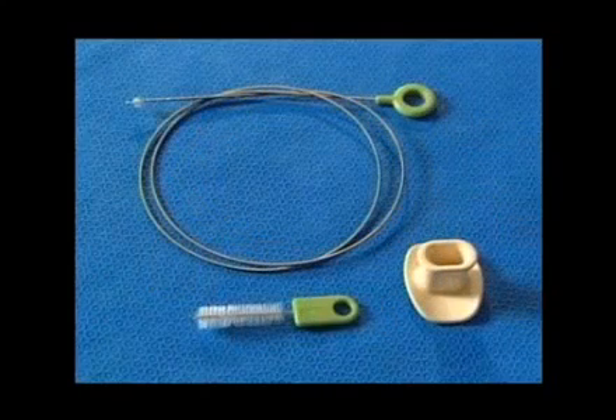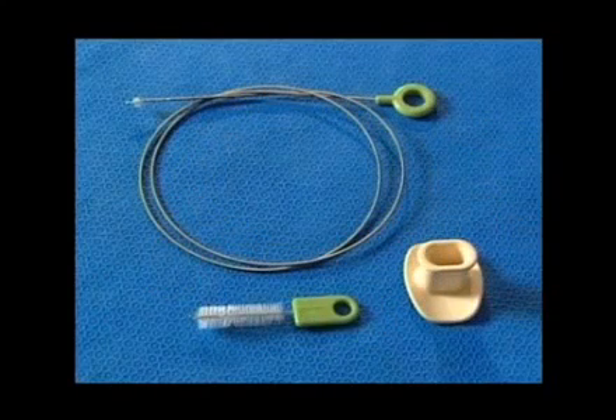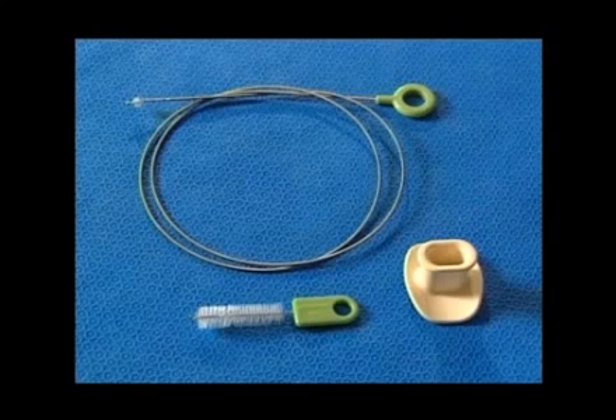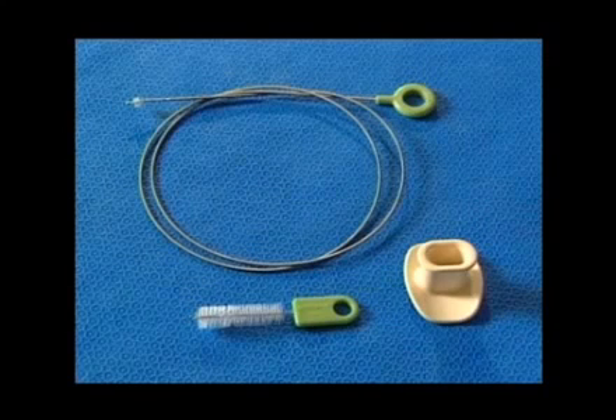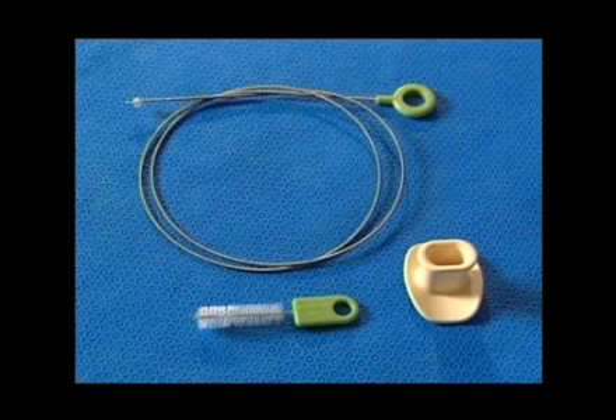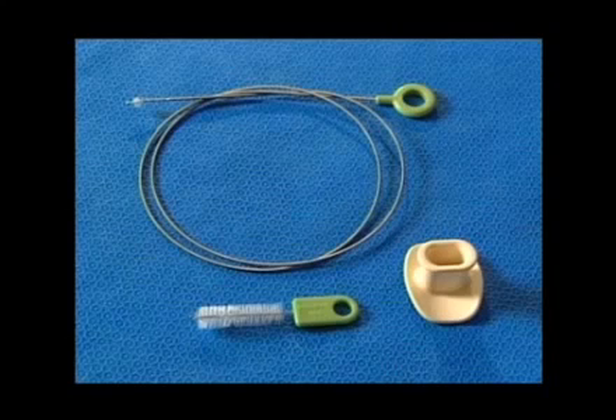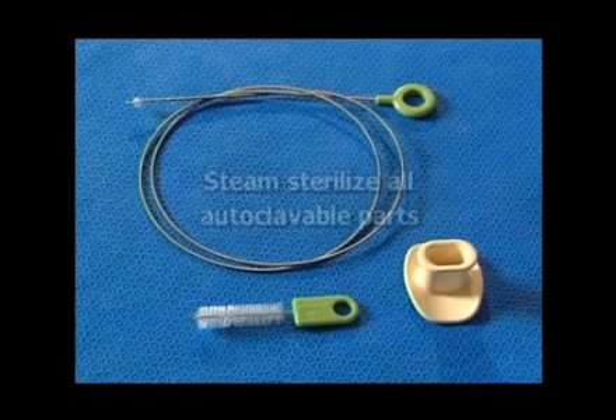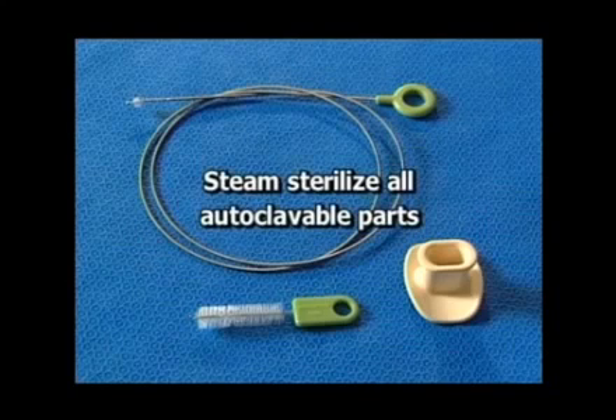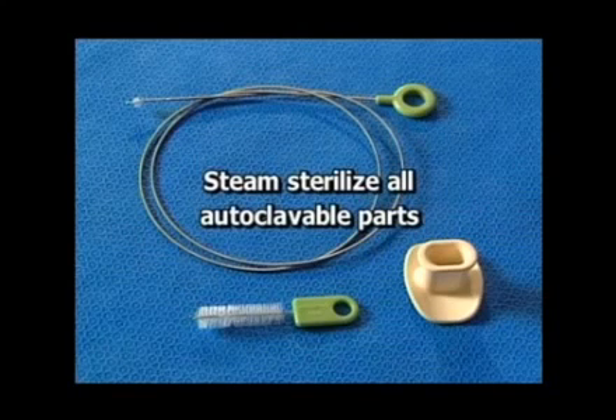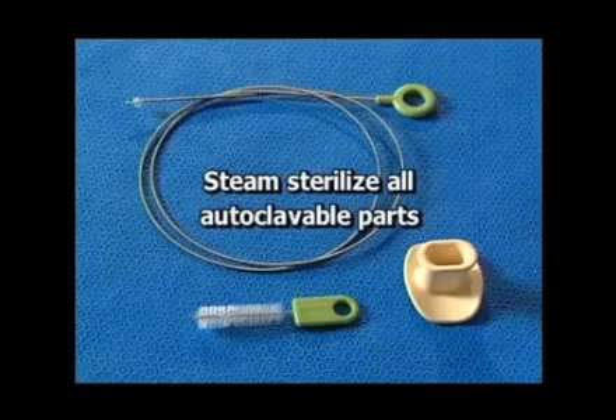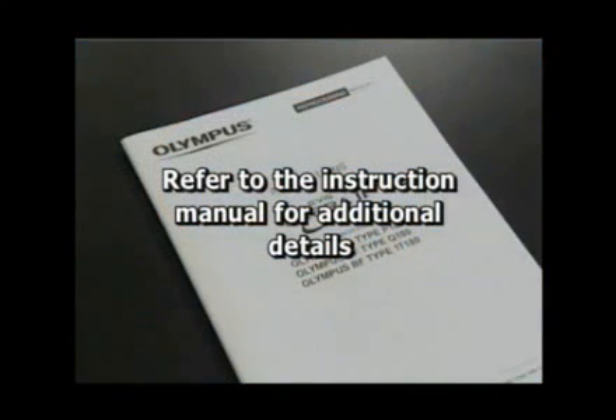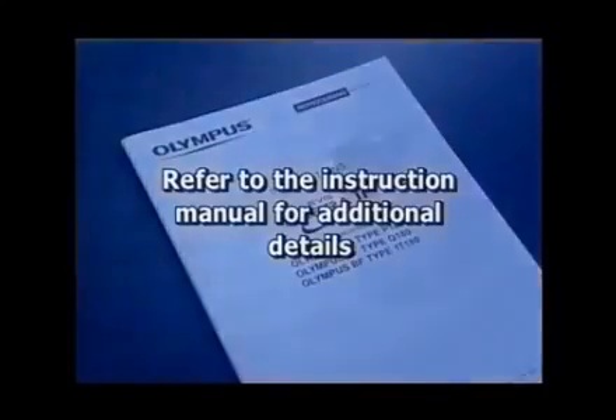This leaves mouthpieces and reusable reprocessing items such as reusable cleaning brushes to be reprocessed. These items should be thoroughly cleaned in detergent solution and then rinsed and dried. Since these articles are autoclavable, it is recommended that they be appropriately wrapped and subjected to steam sterilization. Refer to the instruction manuals detailing these items for further information.